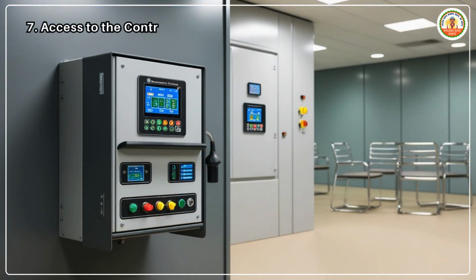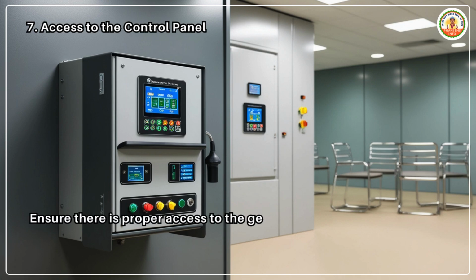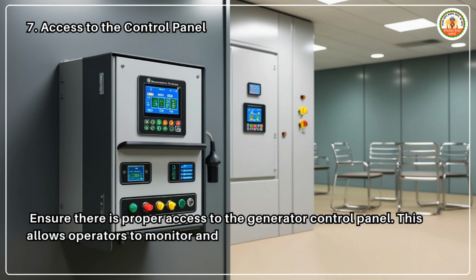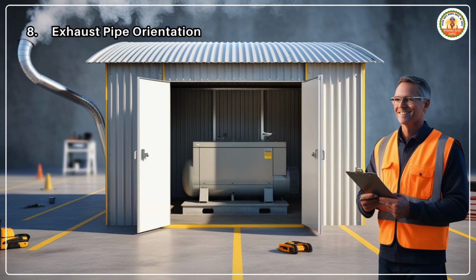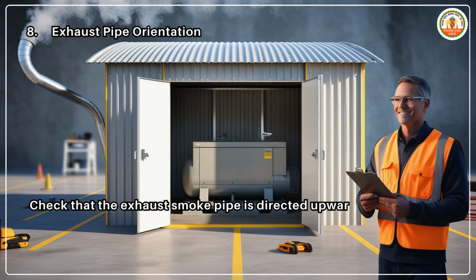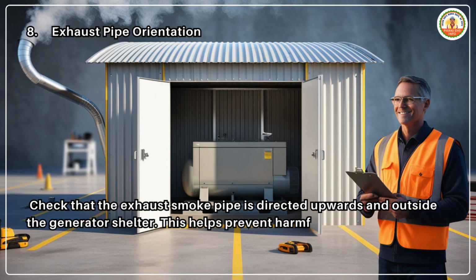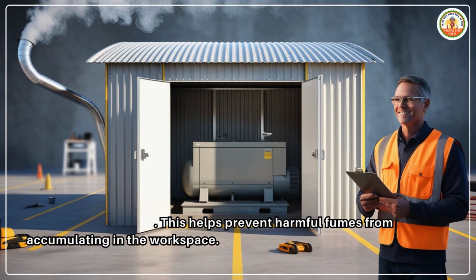7. Access to the control panel. Ensure there is proper access to the generator control panel. This allows operators to monitor and control the generator easily and safely. 8. Exhaust pipe orientation. Check that the exhaust smoke pipe is directed upwards and outside the generator shelter. This helps prevent harmful fumes from accumulating in the workspace.